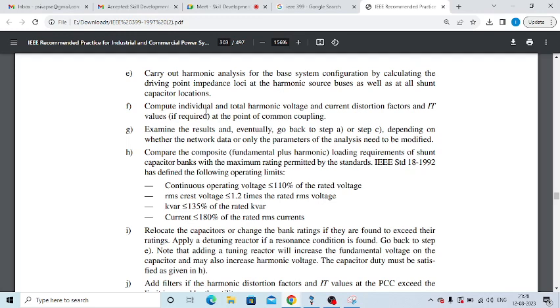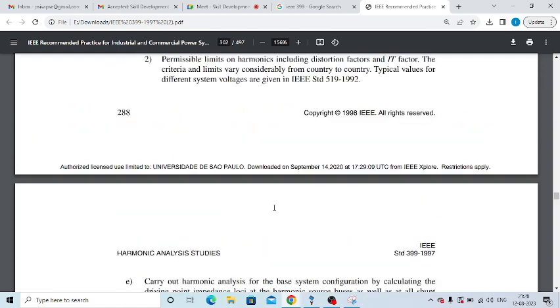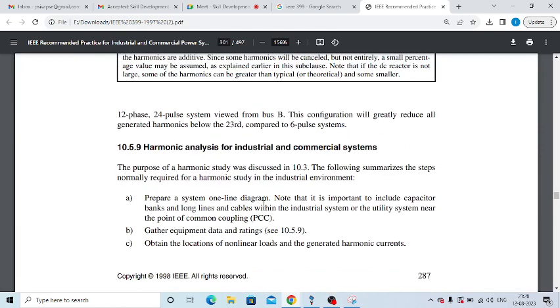So after running the harmonic analysis, we have to calculate the total harmonic distortion and the individual harmonic distortion, and check whether it is within the limit or not. The calculated value we need to check against the value provided by the utility, whether it is acceptable or not. If acceptable, then it is fine. If it is not acceptable, then again we have to come to this location from the single line diagram.